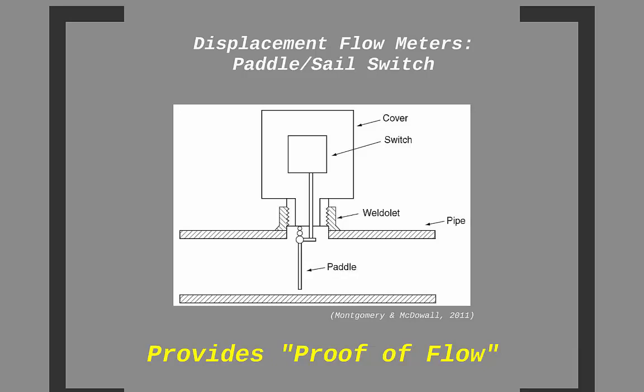A paddle flow switch can be used in a water system. When flow occurs, the paddle will be displaced by the flow of the water and subsequently close a switch. That switch will close an electrical circuit, which could then send a signal to the chiller's controller that flow has indeed been proven. The same configuration of a sensor can be used in an air system, but such a switch is often then referred to as a sail switch.